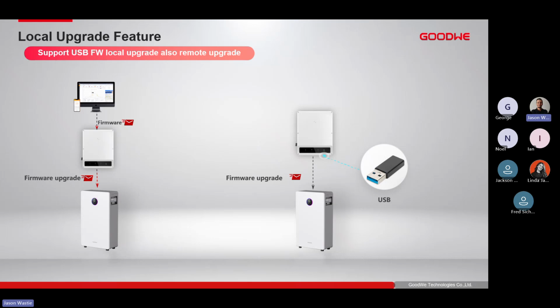All of our batteries will only work with the GoodWe inverters. So a GoodWe battery works with the GoodWe inverter only. However, the GoodWe inverter can operate on many different batteries. With regards to firmware updates and how we can update these inverters and batteries, our batteries can all be updated remotely. We can do it via our online platforms. We can do it via the SEMS Plus app. We can do it via SolarGo when we are commissioning the system. Should there be any requirement for an update on any firmware on any of our products, provided the inverter is online, we can do everything remotely. However, we can also do it on site locally.